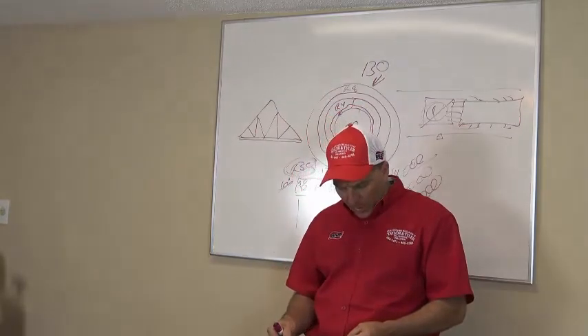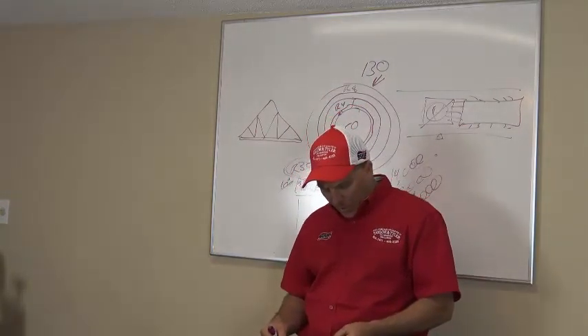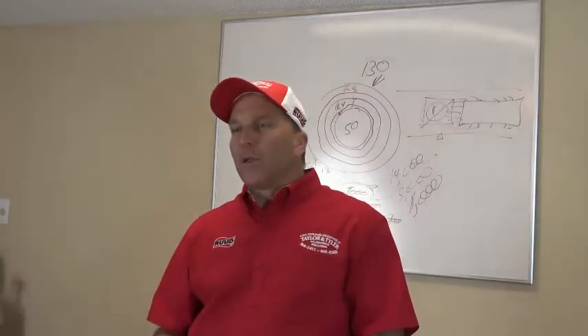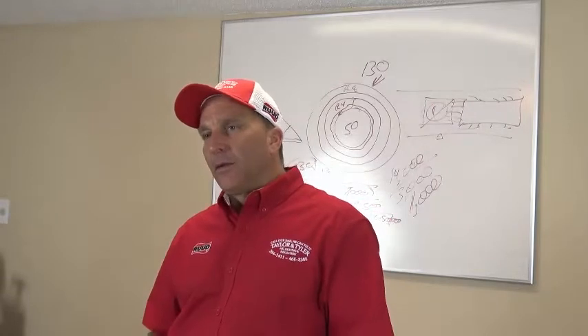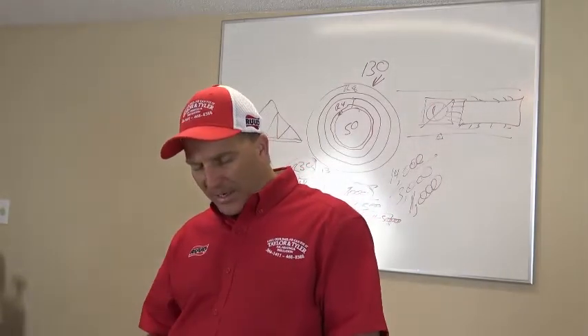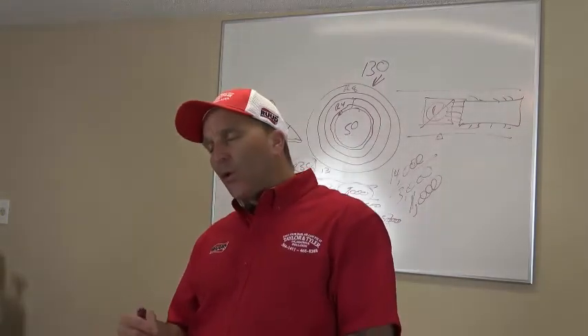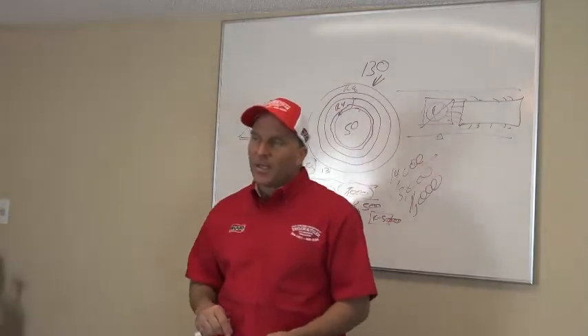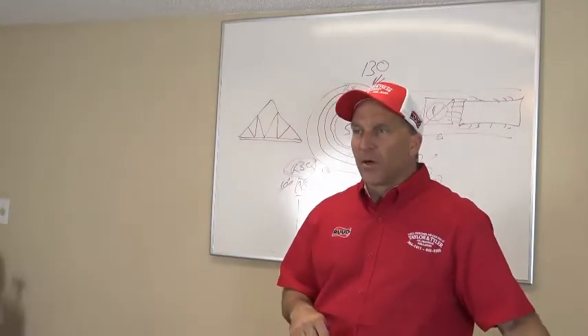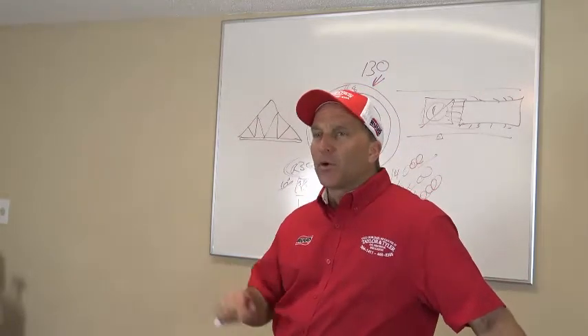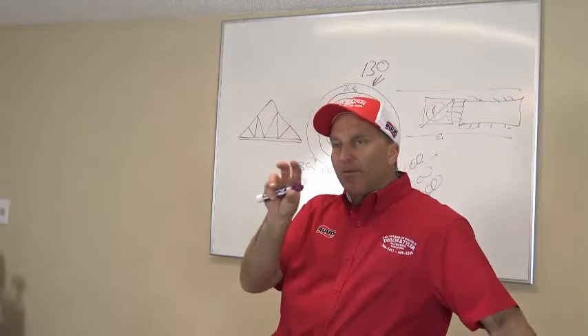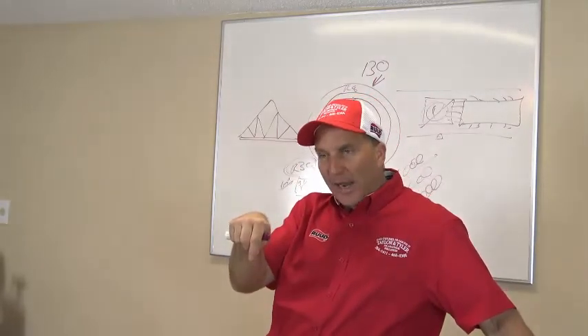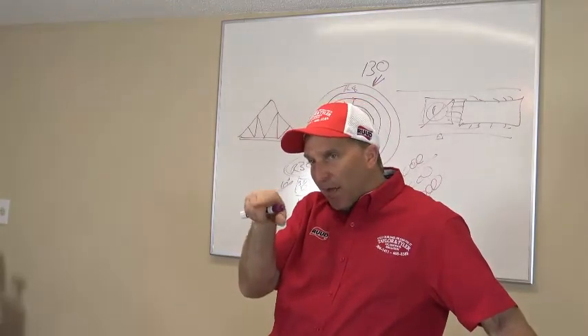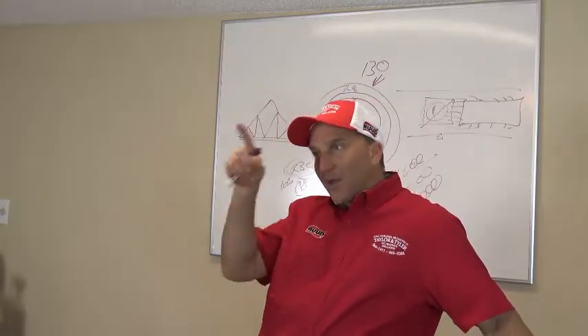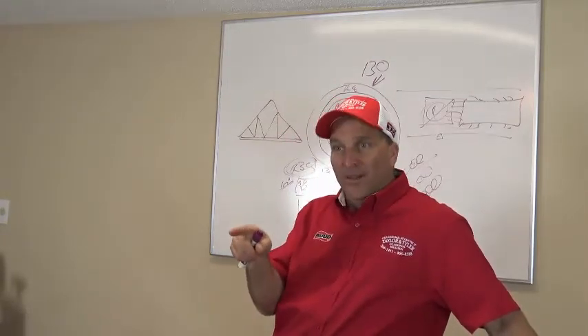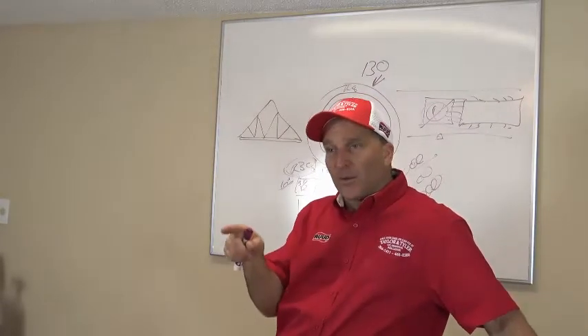Your blower motor. I want to know if it's okay, loose, bearings, or noisy. Well, as it's turning, it could have bad bearings in it. Or the wheel, which is the next one, the blower wheel: clean, dirty, or filthy. Well, the blower wheel could be loose too. Because a lot of times that loud noise when that blower wheel comes on, it's the blower wheel, not the blower motor making the noise. What's happening is the hub of the blower wheel, the actual hub that screws down to the shaft, is spinning at, let's say, 100 miles an hour, but the wheel itself is spinning at 90 miles an hour. So it's as it's running. That's what you're going to hear. Then when you stop, boom, it stops.